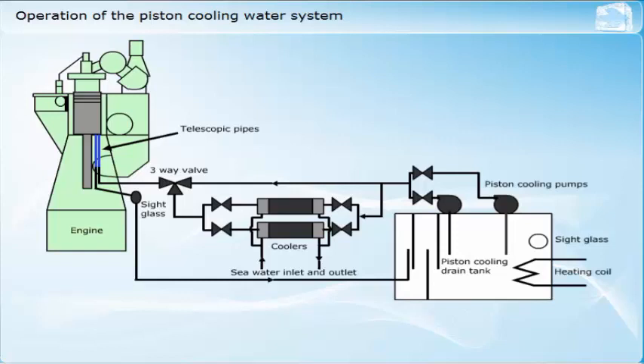Once the tank is at normal level and the valves have been correctly set, the pump can be started. Continuous flow of cooling water through each piston is essential for continued operation, and sight glasses are normally fitted in the return pipes so that flow can be monitored. The temperature is usually monitored at each cylinder, and the cooler bypass is used to adjust it. This basic system shows the temperature being manually controlled.